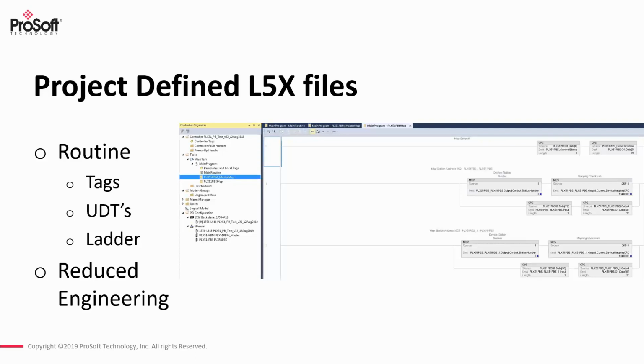You don't have to sit there and try and figure out what data is where, and you get a clearly defined tag within your Studio 5000 environment that lets you know, okay, this Profibus slave data, I've got 16 bytes of information from it, and it goes ahead and puts it into a tag for you. So really the purpose of this is to reduce overall engineering time and commissioning time. So the faster we can get these things integrated, the faster you guys can move on to working on other stuff.